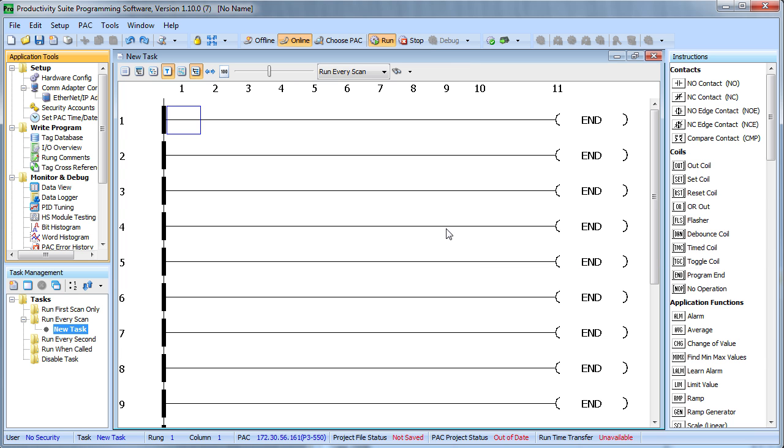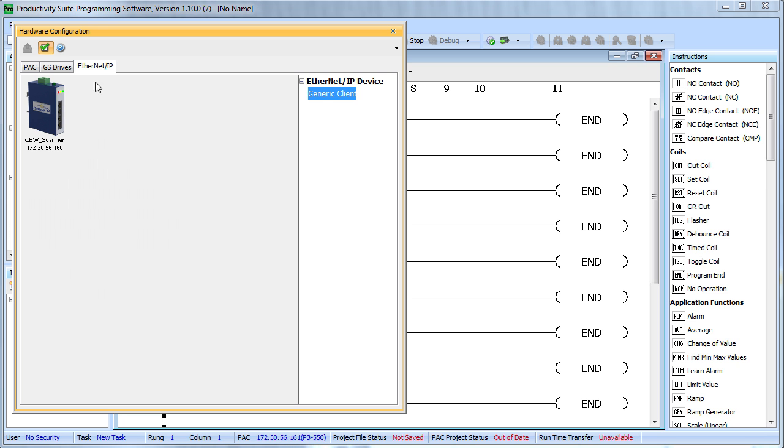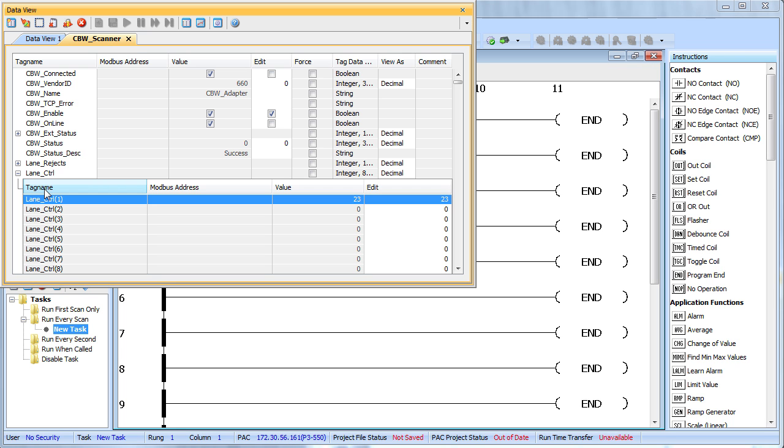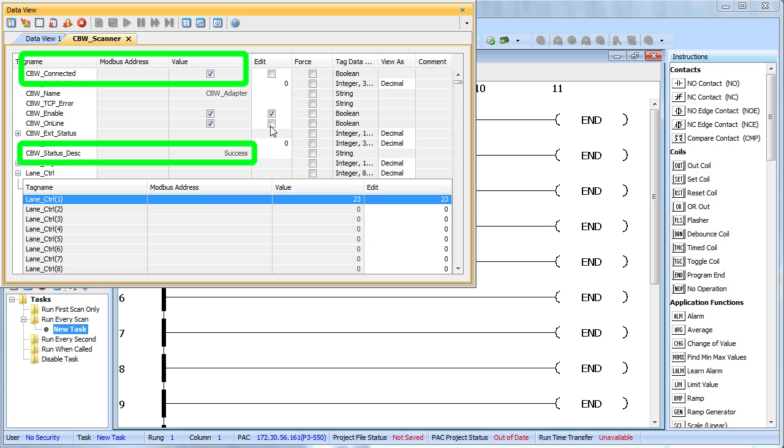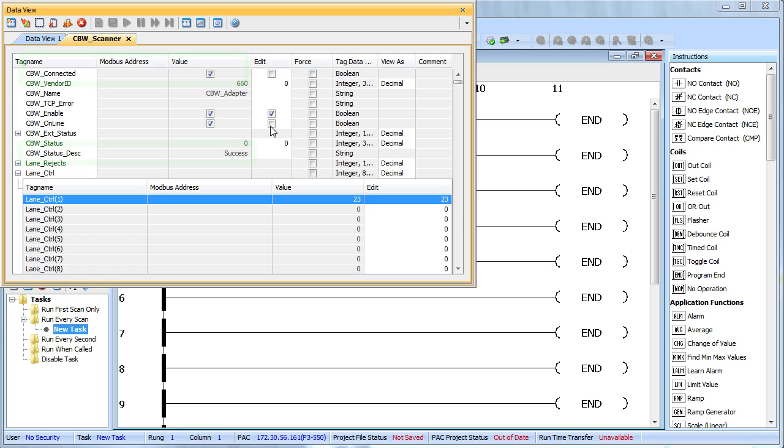That's the beauty of using this IO or implicit Ethernet IP messaging. This is great for real time monitoring of Ethernet IP encoders, Ethernet IP VFDs, Ethernet IP Remote IO and other controllers that adhere to the Ethernet IP standard. And the Productivity 3000 makes it so easy. All we did was configure the hardware by dragging a generic client in here and fill in the blanks. Then in our ladder code, all we have to do is enable the scanner by toggling this Boolean value right here and then we can go check that we actually are connected and that the connection was successful. Given that, we just dropped data into the arrays and it gets transferred between the scanner and the adapter in the background automatically.